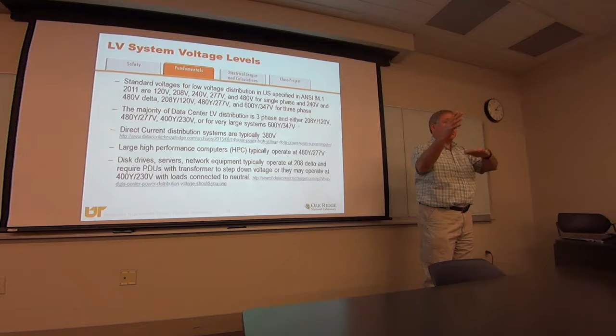So what's the difference between 208 and 240? 240, okay. Is there a difference? Let me go forward here just a second. Because I see those in... Page down. There we go. You see, this is a delta transformer I've got. These are the coils, and the wires are literally run like that. If you trace the wires on a transformer, that's what they do. Now this is a 480 volt delta.